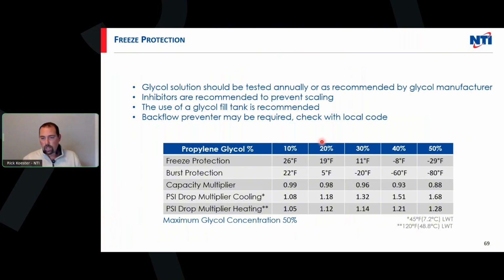So freeze protection is a big conversation. Anytime we have water pipes running outdoors and we lose electricity or something, we want to make sure we have some protection there. Depending on the region, we push contractors to reach out to whoever's glycol. I'm not sure what Emco has available as far as a glycol, but there are recommendations typically right on the bucket that give them all the data they need to make sure the system's properly protected.